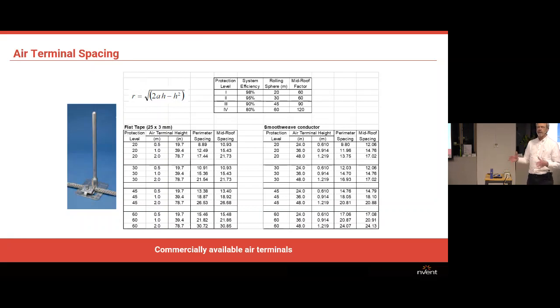This table shows you how far apart those rods can be depending on their height to give you the required level of protection. And as I said, the right-hand table is for the smooth weave conductor system, which has rods that are 610 millimeters tall, or 914, or 1.21 meters, whereas the flat tape system is rounded at 0.5, 1 and 2 meters. The reason for that is metric system for flat tape, and the US uses imperial measurements, so they're actually based on multiples of feet rather than millimeters. And I should say, if you are using a different size rod, you can apply that formula up the top left there to determine their spacing.